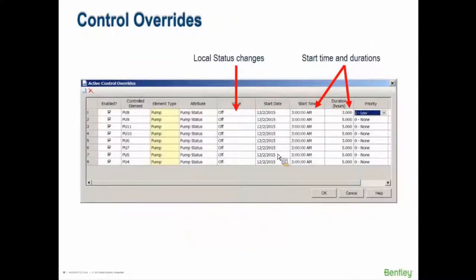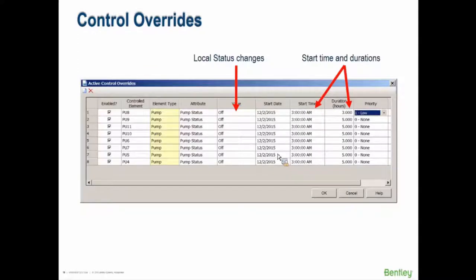Sometimes you want to change how you're operating the system. You can turn things off and on at certain times to override the control statements built into the model. If today is going to be different — you want to turn the pump on or off at a different time — you can do that. There are also priorities: if two control statements conflict, the one with the higher priority wins. So a higher-priority command to turn on at a specific time will override a tank-level-based trigger. That's the value of this real-time operations tool, and people are starting to use it now.